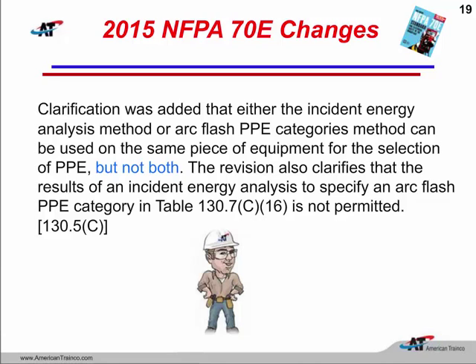This is also going to be reflected on the label that we're going to see in a little while. So if we're going to do the incident energy method, then we're going to see a number in calories per centimeter squared. That is the number that we're going to have to protect ourselves against. If we are going to use the PPE category method, which a lot of people call the table method, then we are going to see a PPE category, 1, 2, 3, or 4. And you can use either method. That's your choice. But you cannot use both on the same piece of equipment. And that label is going to reflect that, and we're going to see that coming up.